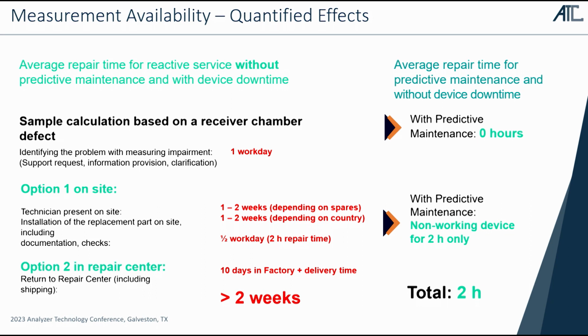If we use a predictive maintenance approach, we get the information 2 weeks earlier, knowing that there will be a problem upcoming. The service technician can order the spare parts in time. The analyzer is still running perfectly, no problem at all. Then the spare parts arrive at site, the technician can replace the part, and you have maybe 2 hours of downtime. That's a big difference for you. So the analyzer's availability is highly increased, with only 2 hours of device downtime instead of maybe 1 week.